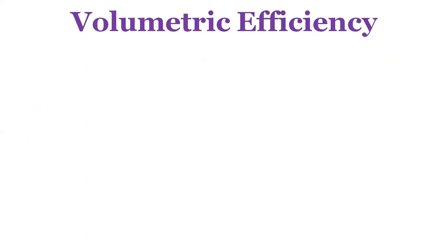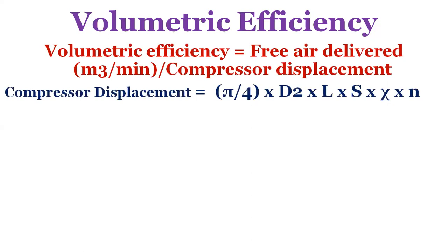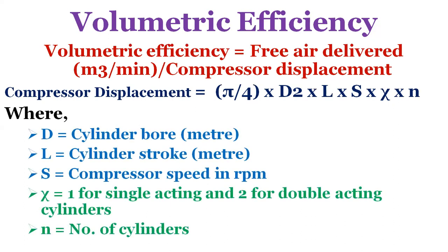Volumetric efficiency is defined as free air delivered (m³/min) divided by compressor displacement. Compressor displacement = (π/4) × D² × L × S × N, where D is cylinder bore (m), L is cylinder stroke (m), S is compressor speed (RPM), and N is the number of cylinders — using 1 for single acting and 2 for double acting. The most practical metric for comparing compressor efficiencies is specific power consumption: kilowatt per volume flow rate.